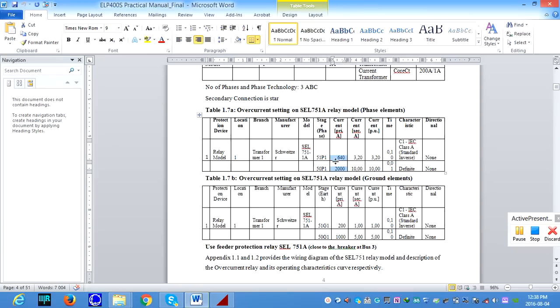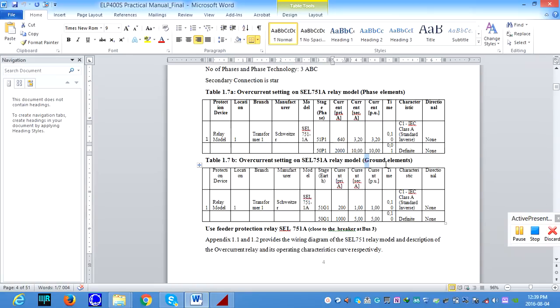Okay, for inverse characteristics, anything from 640 amperes up to 2000 amperes is going to be your IEC inverse characteristics. From 2000 amperes onwards is going to be a definite characteristic. It must be instantaneous.